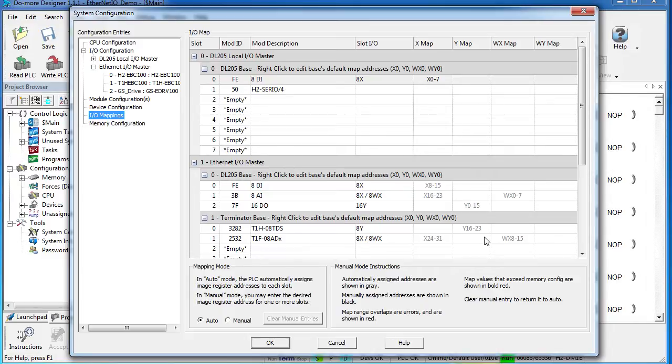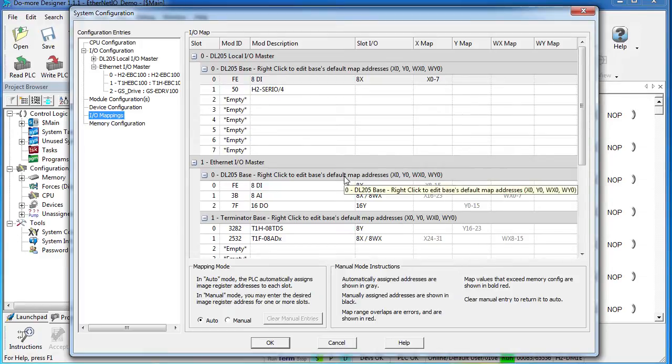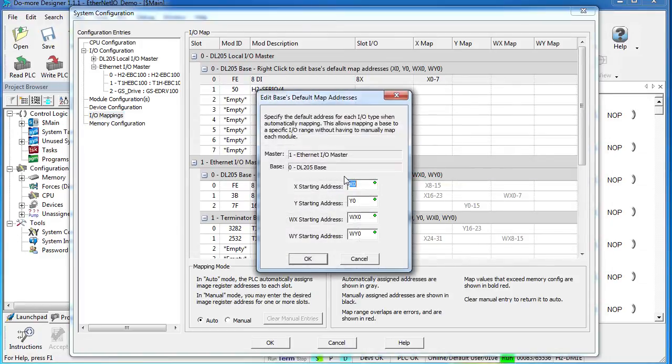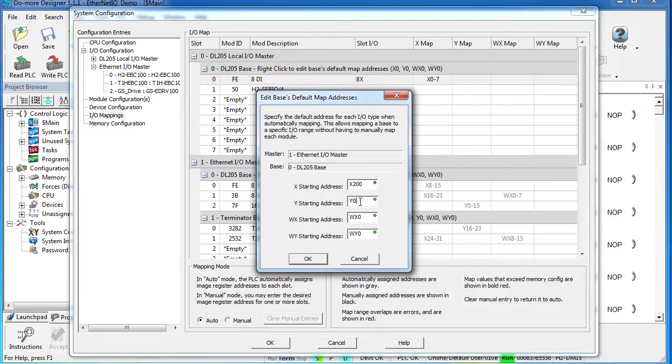So it's a good idea to get in the habit of leaving some addressing space between the bases. So I'm going to right-click on this 205 base, and I'm going to have his inputs start at address 200 and his outputs start at address 200.